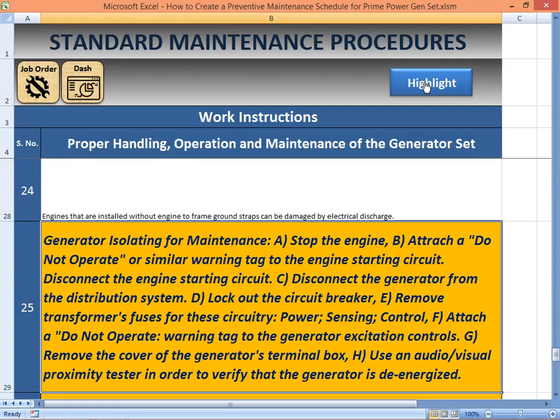This tester must be insulated for the proper voltage rating. Follow all guidelines in order to verify that the tester is operational. You have to make sure that the tester is really operational. Because if you're doing testing and it's not giving you readings, then you are in a precarious situation because you are not sure whether the generator is de-energized or not, and that is very dangerous, a high risk situation.